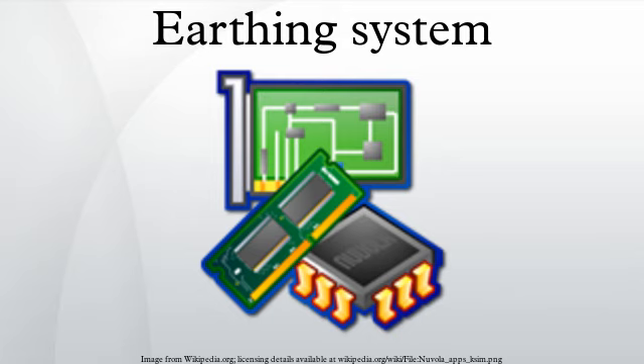This is no longer recommended practice. Laboratory rooms, medical facilities, construction sites, repair workshops, mobile electrical installations, and other environments that are supplied via engine generators where there is an increased risk of insulation faults, often use an IT earthing arrangement supplied from isolation transformers. To mitigate the two fault issues with IT systems, the isolation transformers should supply only a small number of loads each and should be protected with an insulation monitoring device.